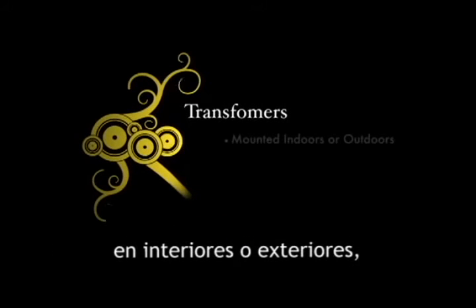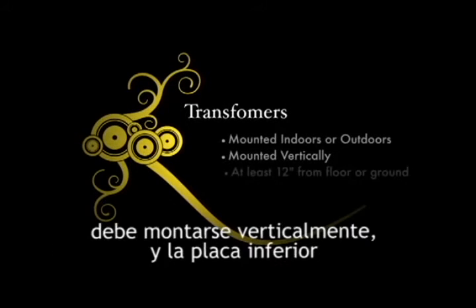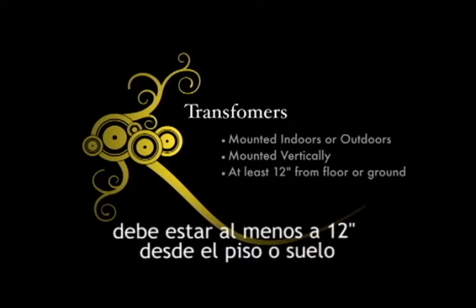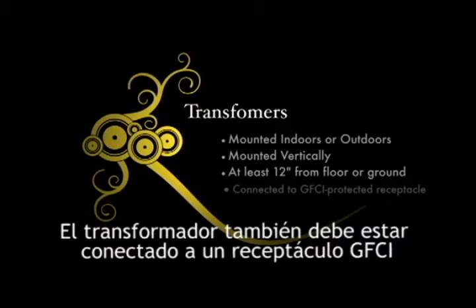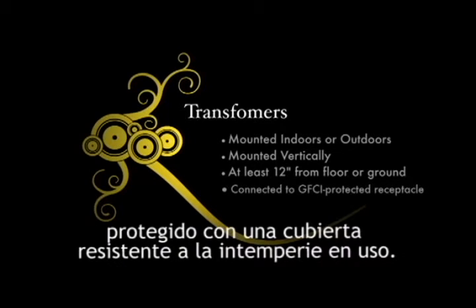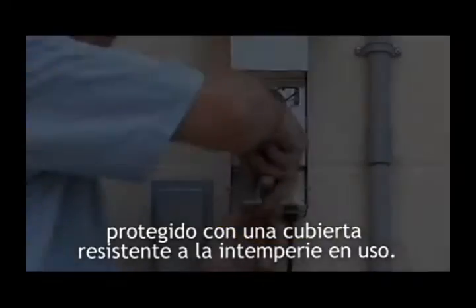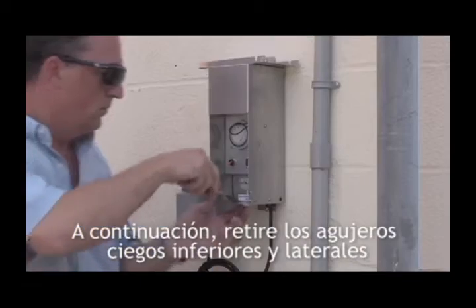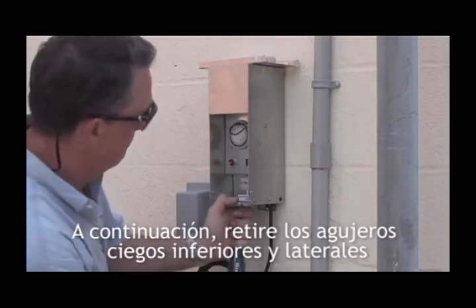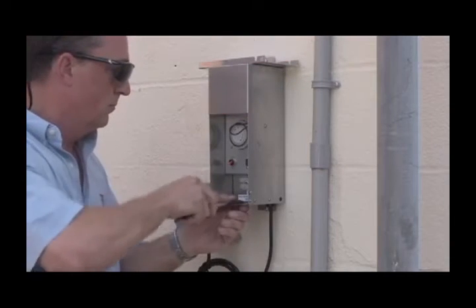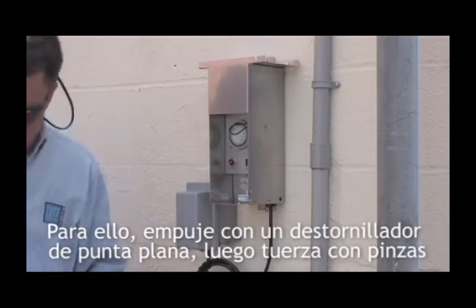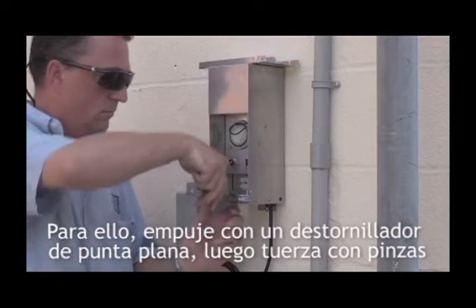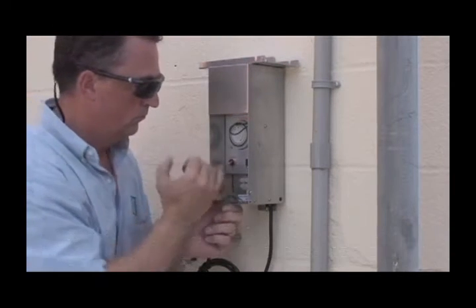Keep in mind that transformers can be mounted inside or outside, must be mounted vertically, and the bottom plate needs to be at least 12 inches from the floor or ground. The transformer must also be plugged into a GFCI protected receptacle with in-use weatherproof cover. Next, remove bottom and side knockouts. Do this by pushing out with a flat blade screwdriver, then twisting off with pliers.